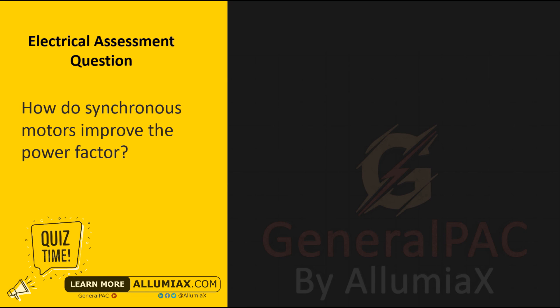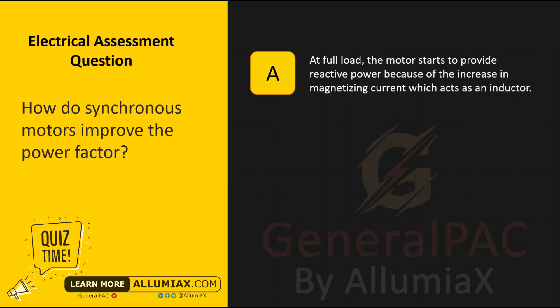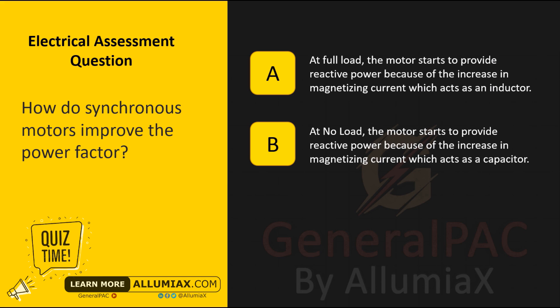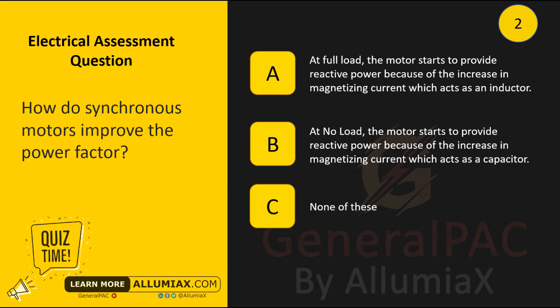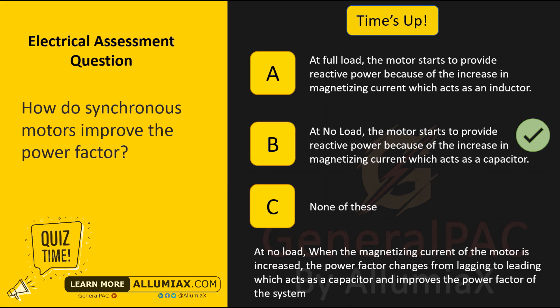How do synchronous motors improve the power factor? A: At full load, the motor starts to provide reactive power because of the increase in magnetizing current, which acts as an inductor. B: At no load, the motor starts to provide reactive power because of the increase in magnetizing current, which acts as a capacitor. The answer is B. At no load, when the magnetizing current of the motor is increased, the power factor changes from lagging to leading, which acts as a capacitor and improves the power factor of the system.